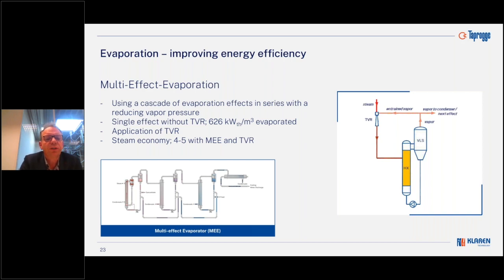If you evaporate water, and this is also in our internal training for new engineers, you can easily calculate that if you want to evaporate 1 cubic meter of water, you need around 630 kilowatt thermal energy to evaporate these 1,000 liters. So that's a huge amount of energy, and this energy goes into the phase change between liquid and vapor. And this is exactly where you also have to look for improving energy efficiency.